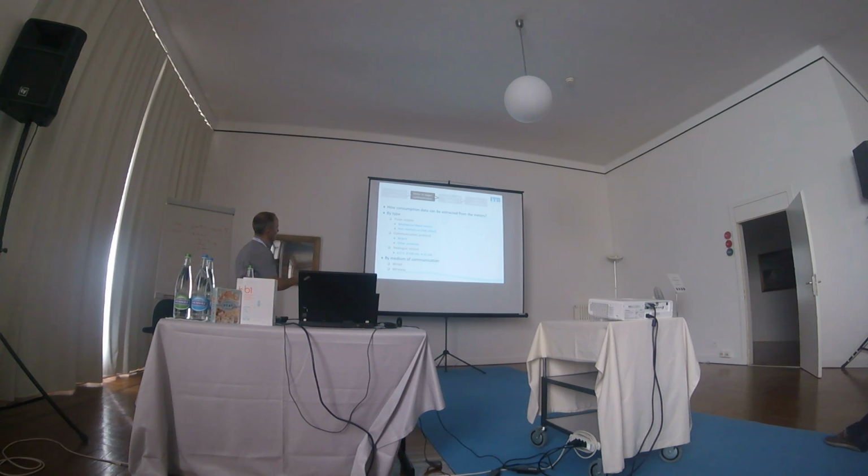The second thing is, okay, now I know that the best solution is to use mechanical meters with a high resolution reading, but how do I take the reading from the meter to the logger? So basically we have three options. The first is to use a pulse output, like the one that you are using, or the commercial pulse emitters that the manufacturers can give you, which are usually based on Hall effect sensors or inductive sensors.